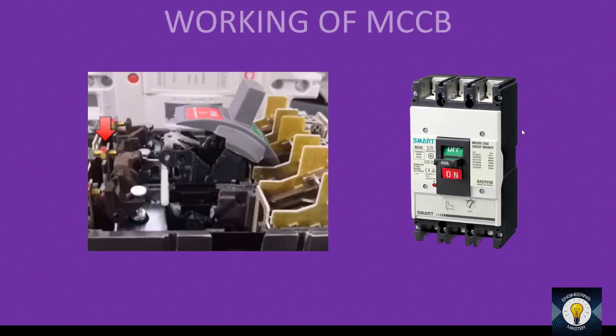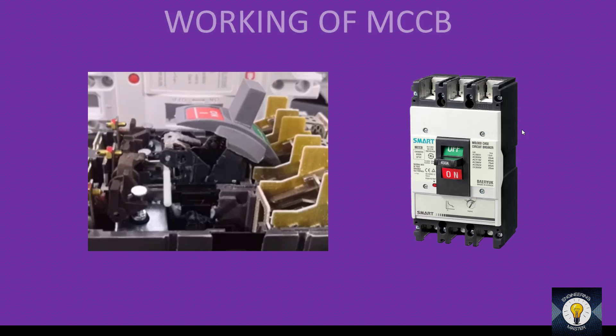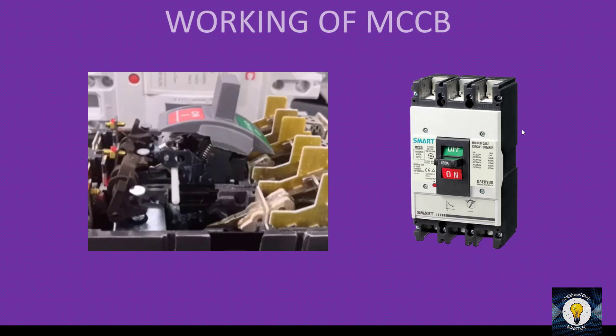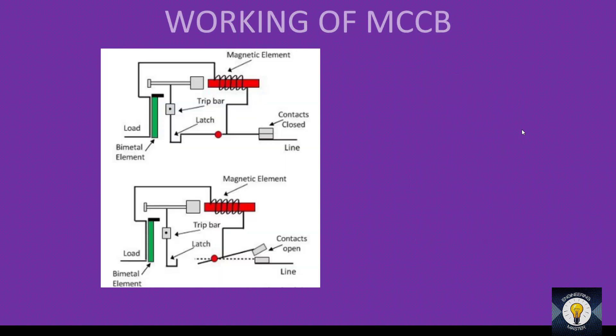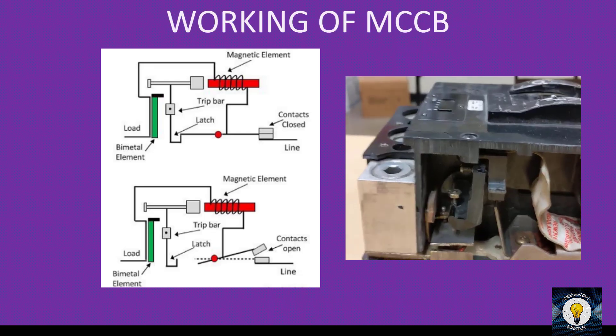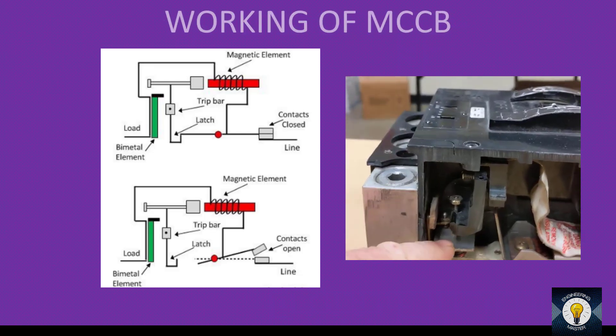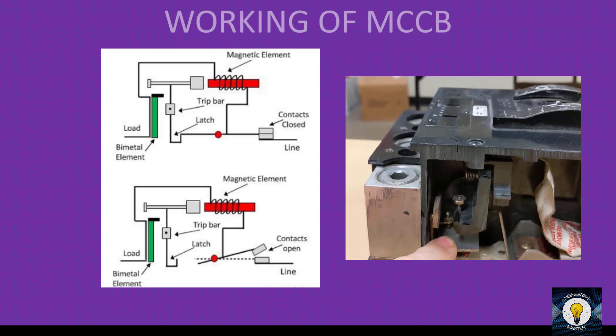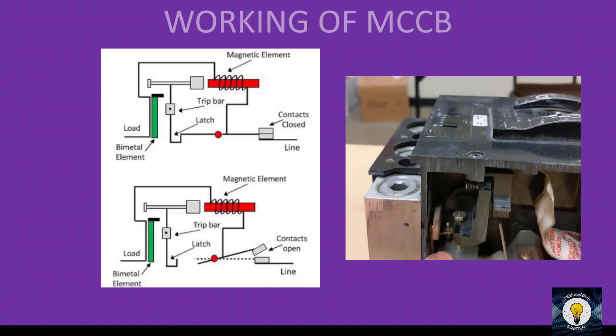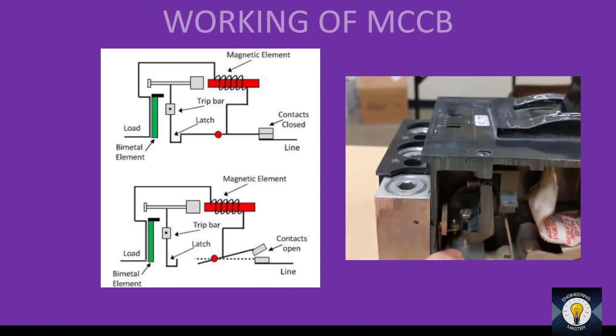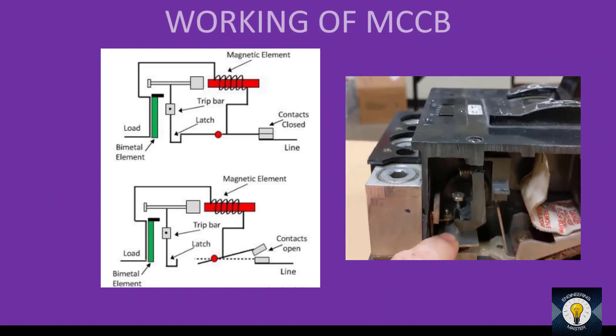Due to the heating and bending of the bimetallic strip, it activates the triggering mechanism and the MCCB is tripped. For short circuit tripping, we use a solenoid-type arrangement. There is a coil with a piston inside. When current passes through the coil, due to electromagnetic force, the piston moves to the center. This triggers the contacts and the circuit breaker is tripped.